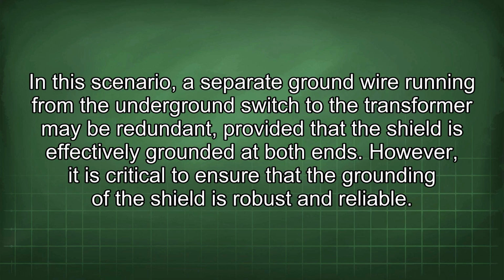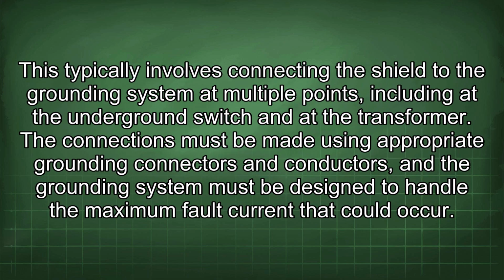In this scenario, a separate ground wire running from the underground switch to the transformer may be redundant, provided that the shield is effectively grounded at both ends. However, it is critical to ensure that the grounding of the shield is robust and reliable. This typically involves connecting the shield to the grounding system at multiple points, including at the underground switch and at the transformer. The connections must be made using appropriate grounding connectors and conductors, and the grounding system must be designed to handle the maximum fault current that could occur.